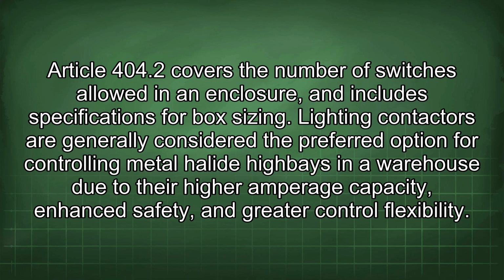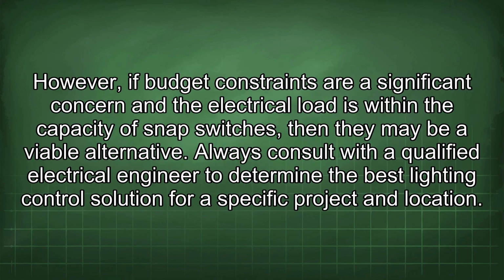Lighting contactors are generally considered the preferred option for controlling metal halide highbays in a warehouse due to their higher amperage capacity, enhanced safety, and greater control flexibility. However, if budget constraints are a significant concern and the electrical load is within the capacity of snap switches, then they may be a viable alternative. Always consult with a qualified electrical engineer to determine the best lighting control solution for a specific project and location.